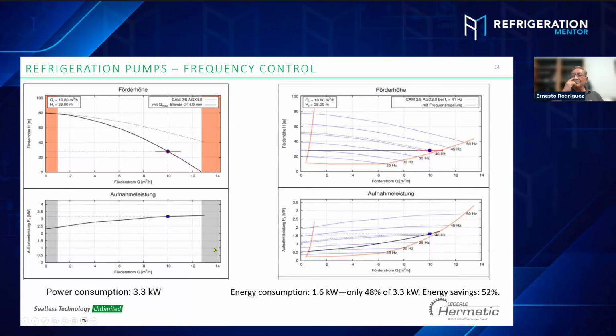Okay, I want to explain right now. We talk about flashing. Okay, this is a good example. Majority of the systems right now try to use frequency drives to save energy. Those are excellent devices to control and save energy. We have a sample right here in this curve with an orifice. The pump is running normally, and we have a consumption of 3.3 kilowatts. But with the VFD, we have a consumption of 1.6 kilowatts. That's an excellent device, but it's very tricky to use VFDs when you use CO2.